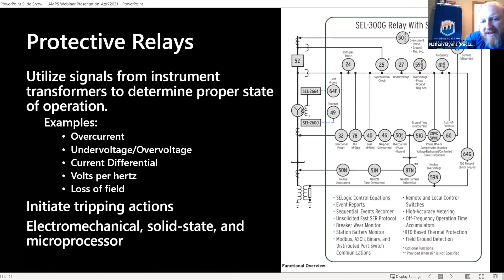Once the protective relay initiates a trip, we have lockout relays, and the lockout relays can combine signals from multiple protective relays and initiate the tripping of a circuit breaker to remove the harmful energy from the system where the fault may occur. It can also initiate other critical systems such as fire suppression.